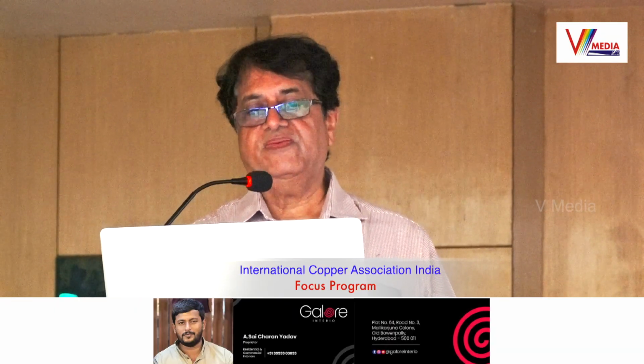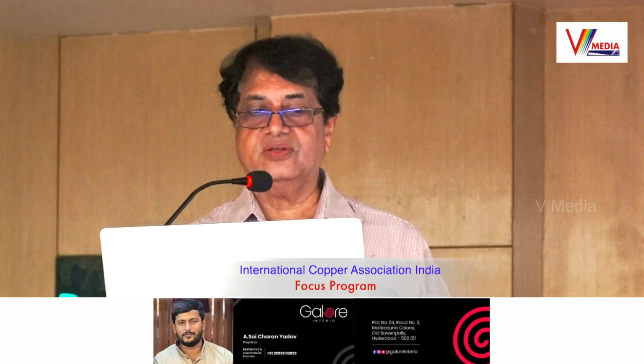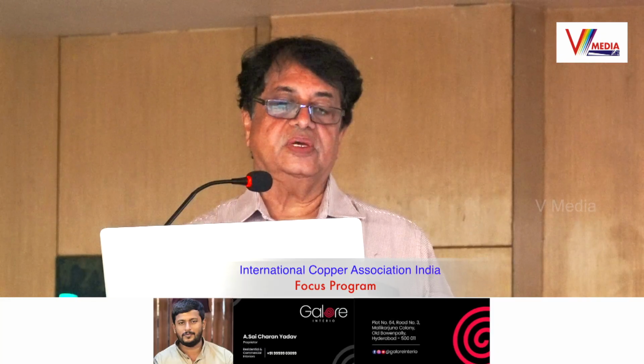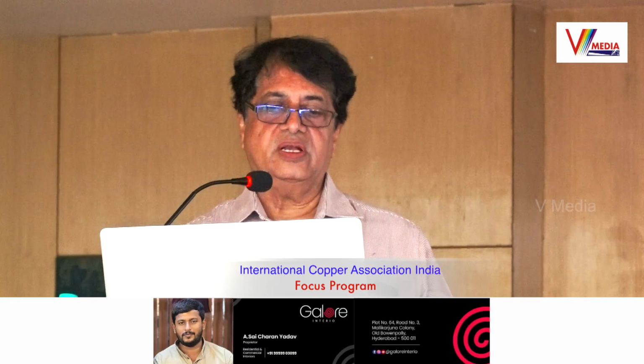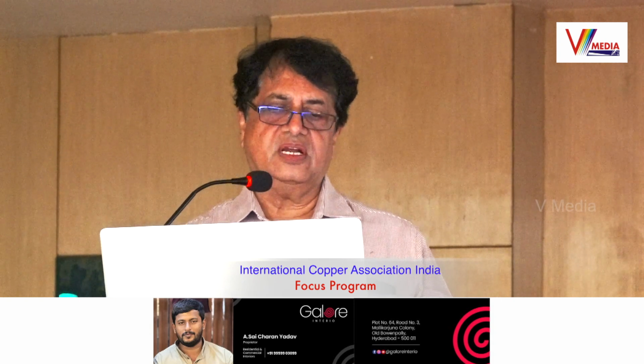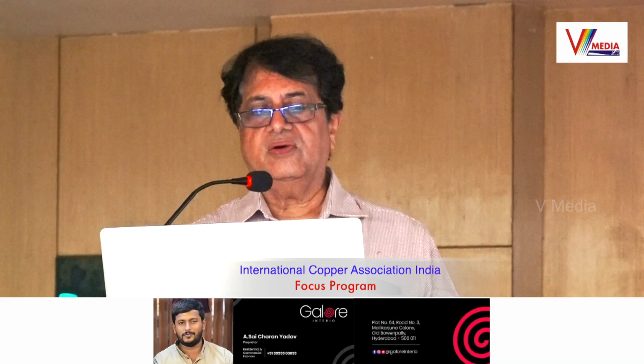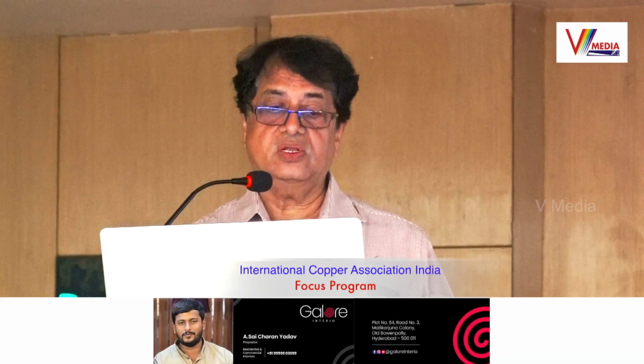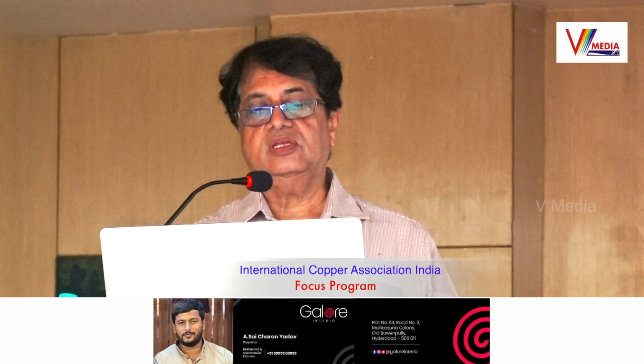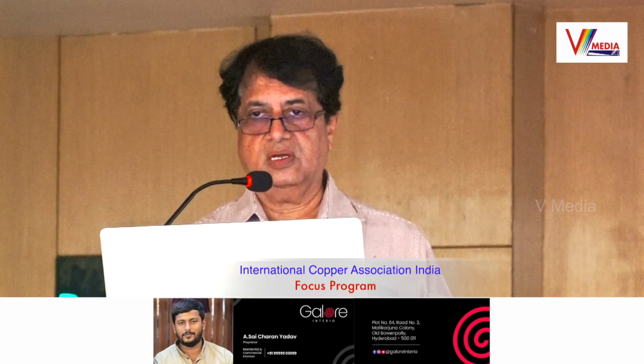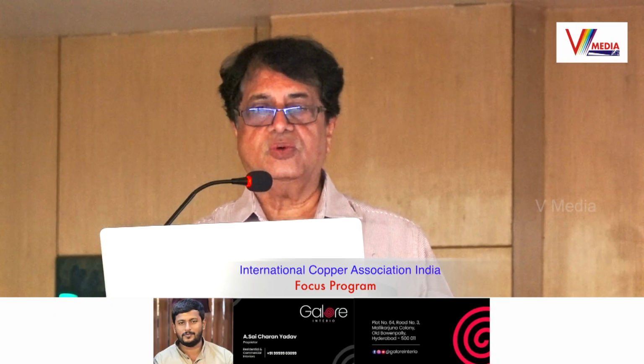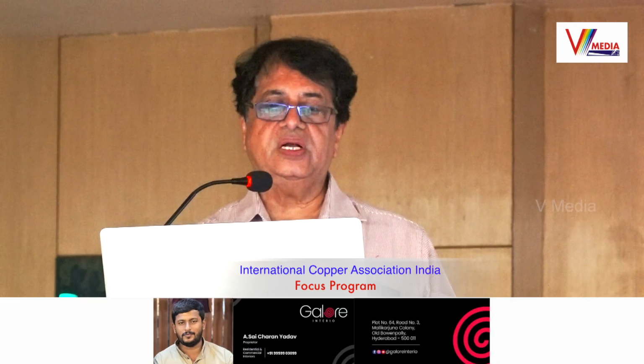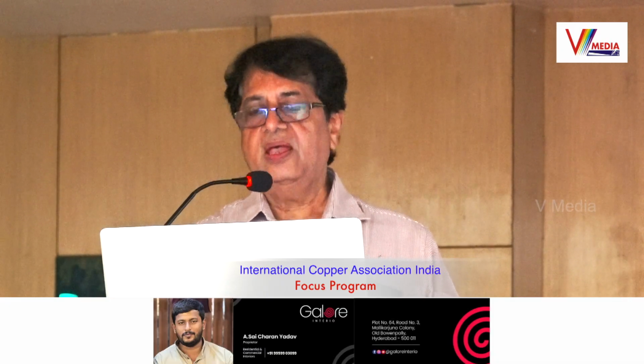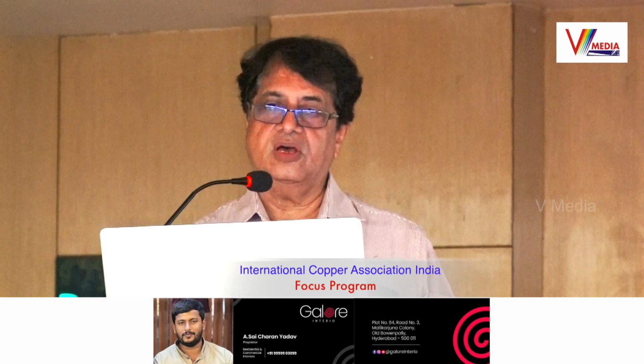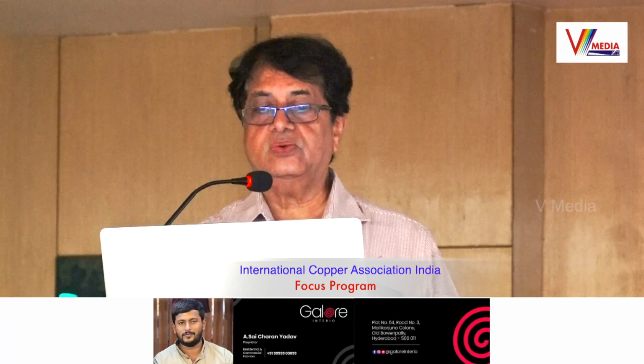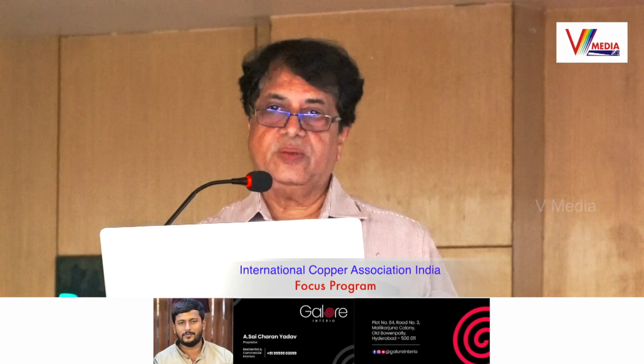Nowadays, high-rise buildings are coming up very, very fast. I have seen so many high-rise buildings coming up in Hyderabad also. And this is one of the pictures of a building from Mumbai. It was originally designed as a 118-storied building. But now the height is restricted to somewhere around 89 or 90 floors. So in the case of such a building, it is not possible to install the distribution transformers at ground level only, because the length of cables or bus duct will be very, very high, and it may lead to voltage drops and loss of energy. So in such cases, it is preferred that the transformer shall be installed on the upper floors also. Even the technical standards published by CEA have allowed transformers to be installed on the terrace floor also.